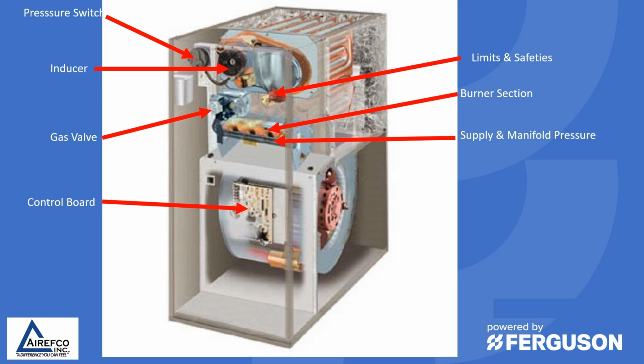Proper supply and manifold pressure is also necessary for the proper burning of the flame on the burner. I usually like to see the supply manifold pressure to be around 10 inches, anywhere from 8 to 10 inches. And then, of course, the manifold pressure is going to vary depending on what type of furnace this is and what type of gas you're using. So double check the data tag on the furnace to make sure that the manifold pressure is set correctly for the correct operation of the furnace.